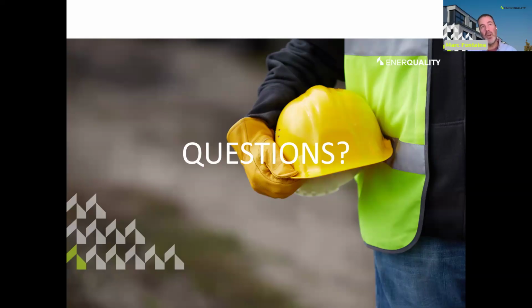So that might seem low, it's a big penalty, but in projects where you have a lot of hot water going down the drain, having a horizontal unit where you can't put a vertical one might still be a good solution in terms of payback. So in a house, maybe not so much, because the hot water load is fairly low. But if you have an application where you have a multi-story building, or maybe a sports center kind of application where you have a lot of showering and so forth, then obviously we do those, and it's of interest in those projects.